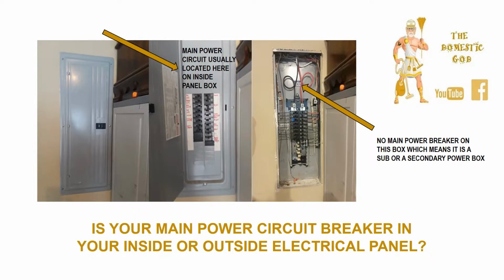The first thing you need to figure out when you're going to change a circuit breaker is your main power circuit breaker in your inside or outside electrical panel box. As you can see right here, a normal circuit breaker box will have a main unit above all the other circuit breakers below it that operate the house. But if you look on this other picture, in my home, there isn't one there, which got really confusing. So mine is on the outside of the house. So you need to go out there and find where that's located at.